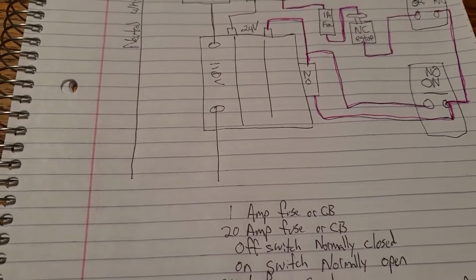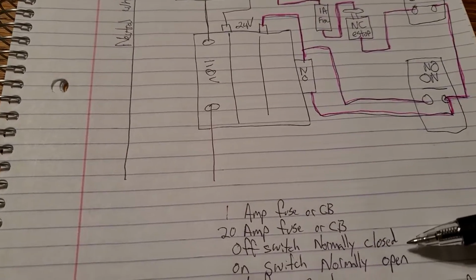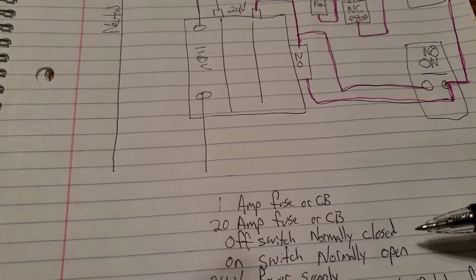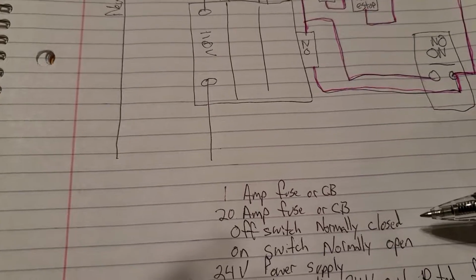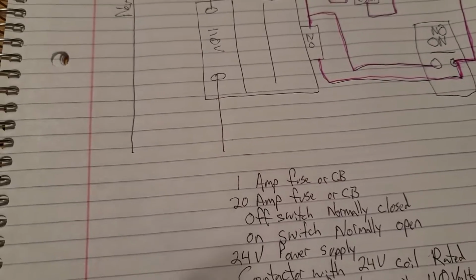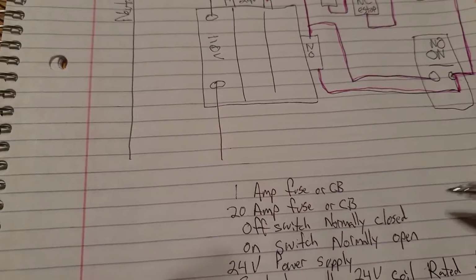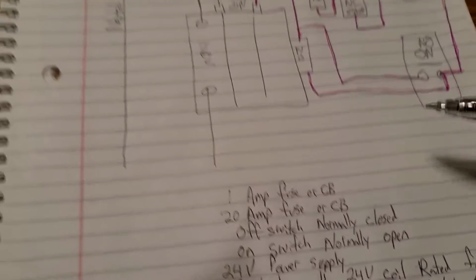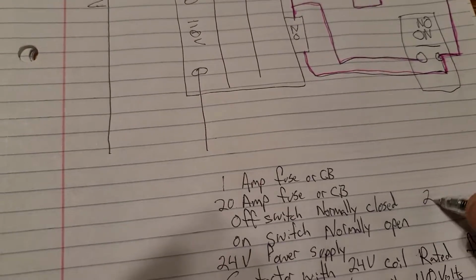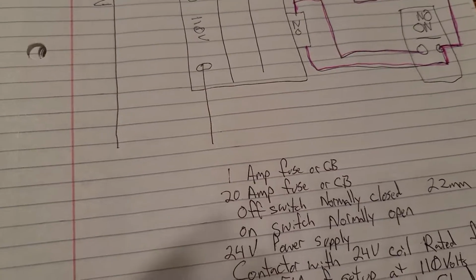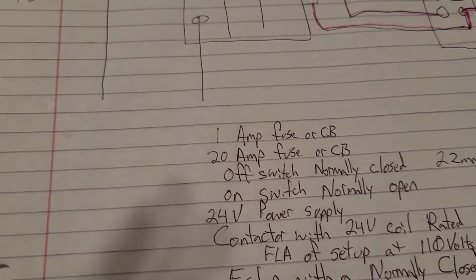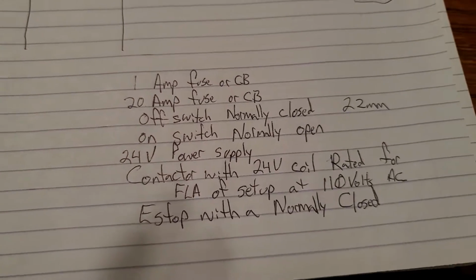Then you also want an off switch that has a normally closed contact. So these are momentary on and off buttons, spring loaded. And then you want to make sure that the off switch is normally closed. I like the 22 millimeter diameter ones. You can get them at Factory Mation. WEG makes really nice ones, or you can get the ones from China, and they're real cheap.